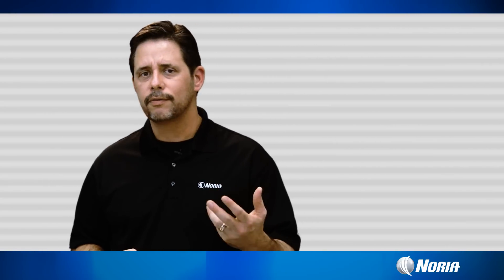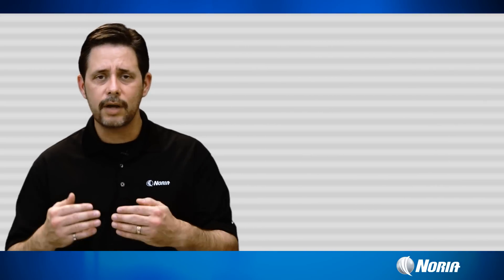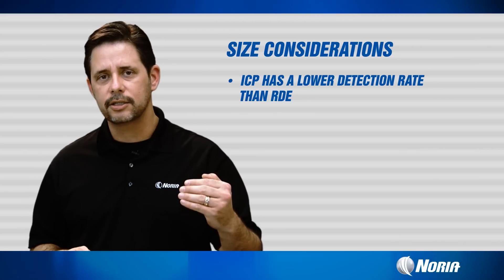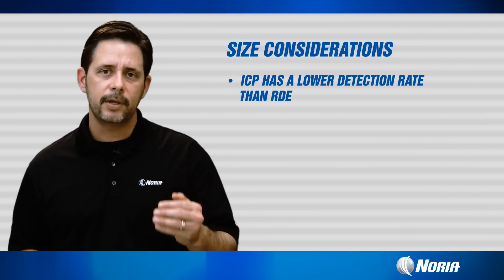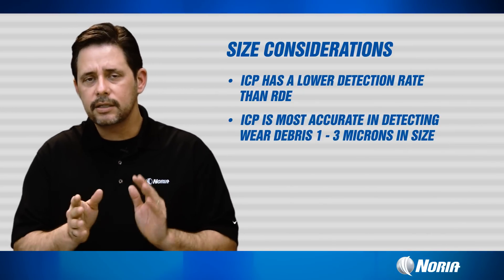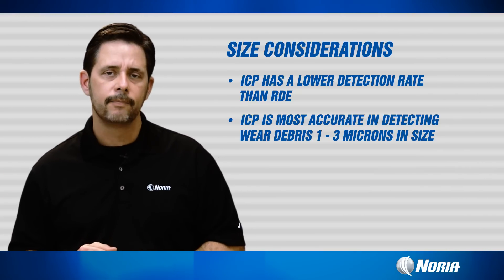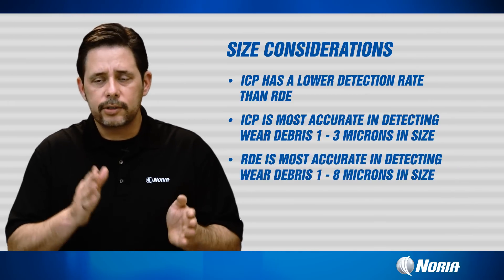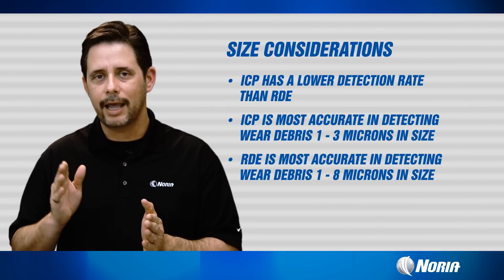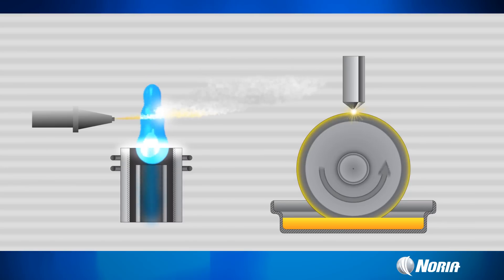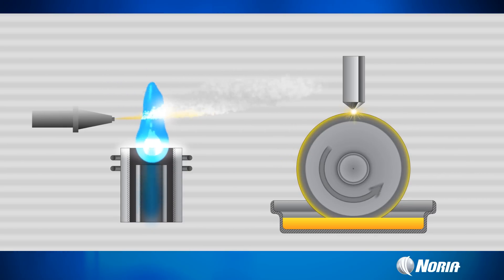The accuracy of these machines is very good, provided that the calibration standard is up to date. Both machines do have size limitations as mentioned earlier. The ICP has a lower detection level than the ROTRODE — it is very accurate from 1 to 3 microns in size, begins losing accuracy up to about 5 microns, and beyond that is essentially blind. ROTRODE spectroscopy is accurate up to about 8 microns, loses accuracy between 8 and 10 microns, and is completely blind above 10 microns. This means we really cannot compare data between a laboratory using ICP and one using rotating disc spectroscopy.